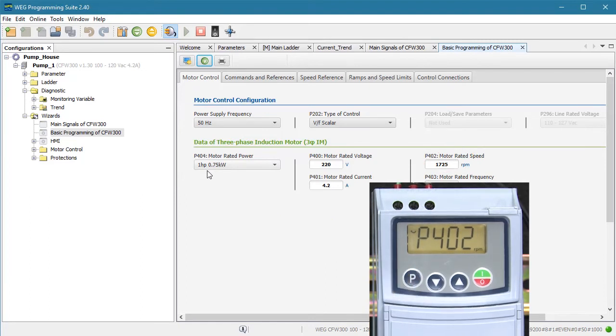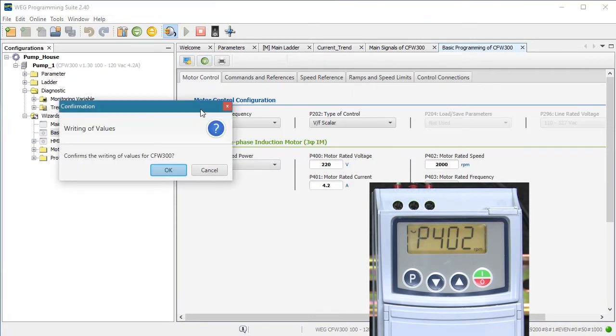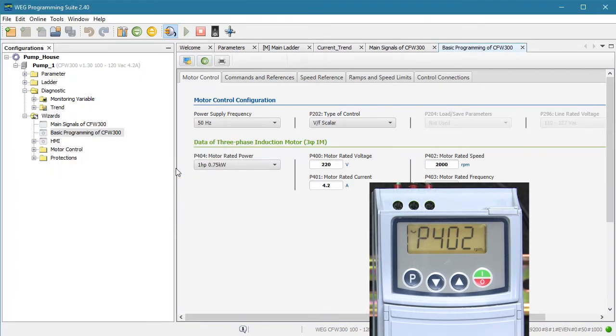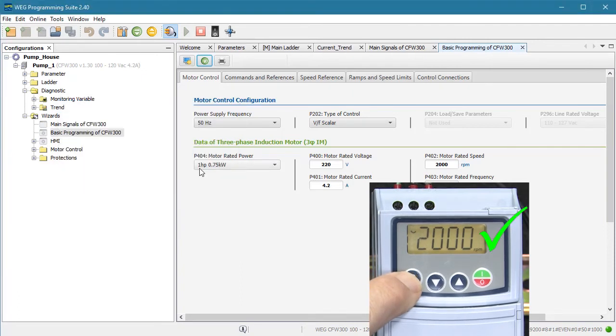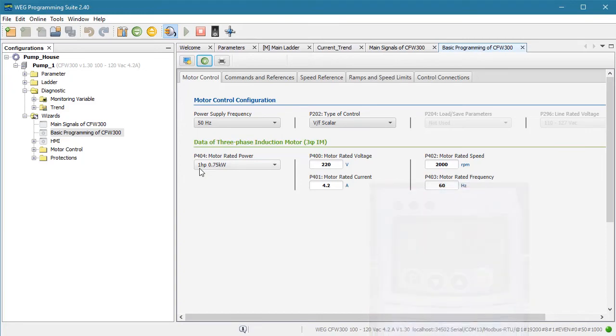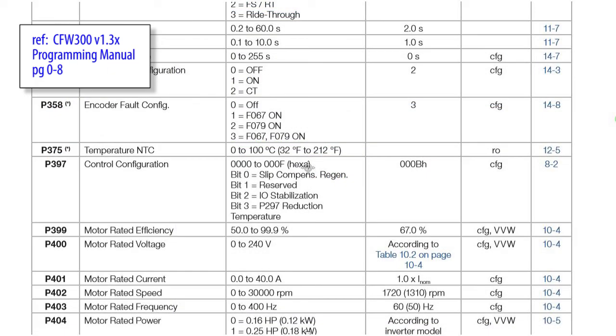You must be outside of editing the parameter, change it in the wizard, write it out, then drop back into it on the drive to see the change. That ensures that important parameters can't be modified in two places at the same time and it applies to any parameter that has this CFG indication in the parameter summary chart.